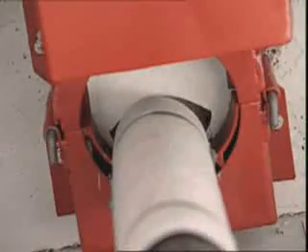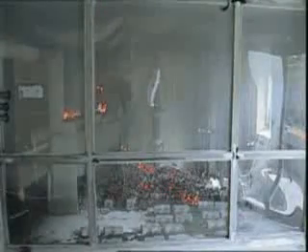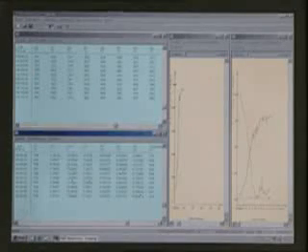After 40 minutes, the temperatures in the test room are falling. After 1 hour, the thermocouples are still recording 420 degrees on the floor, 530 degrees in the center of the room, and 570 degrees underneath the ceiling. After the room is cooled off, we are taking stock.